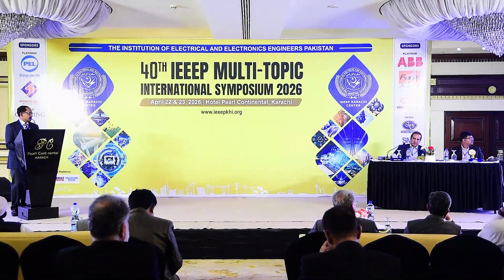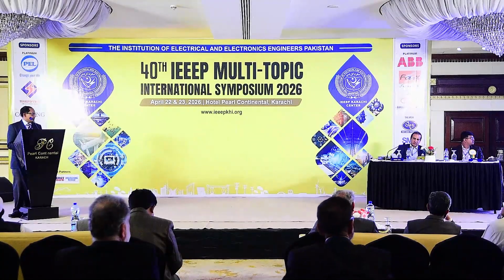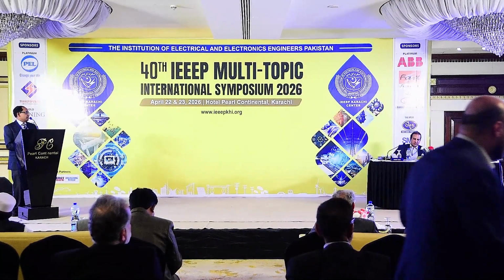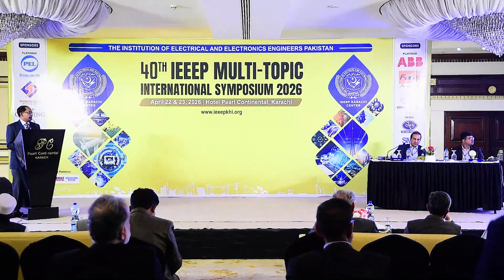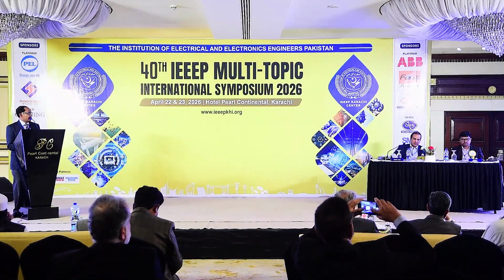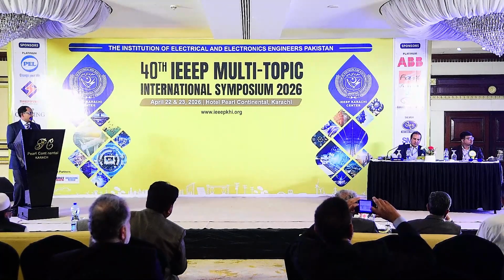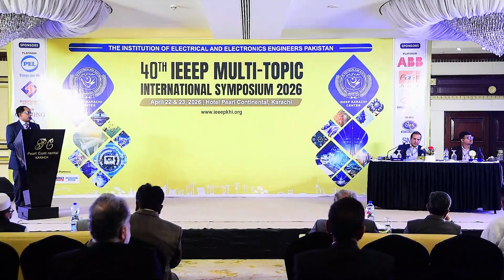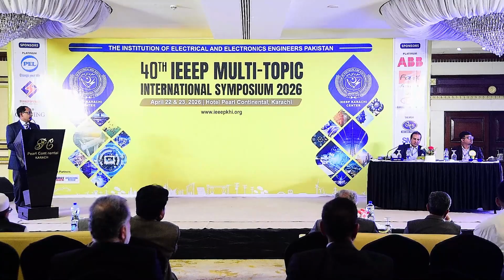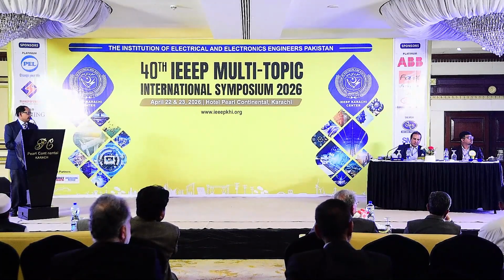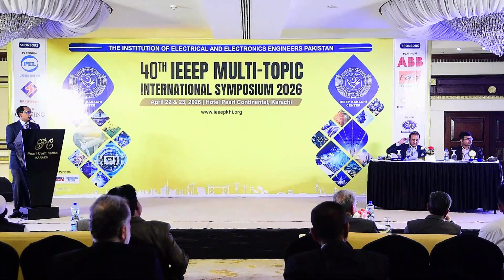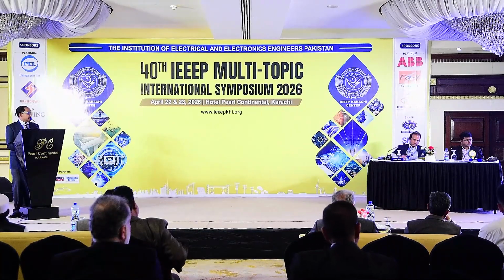Now the virtual synchronous generator mode. In virtual synchronous generator mode, the control system mimics the mechanical dynamics of a traditional synchronous machine. Here BESS acts as the energy reservoir required to provide the rapid power injections or subtractions, controlled through a fast computational controller. The basic concept here runs on the main power swing equation, which has two parts. One is the synthetic inertia control and the second is the droop control mode.